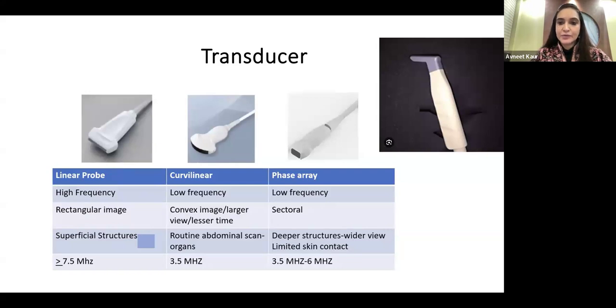So we have three different types of probes available. We have linear probes, curvilinear probes, and phased array probes. And we know that they are all different and can be used for different systems. First we talk about the linear probe. Linear probes have a higher frequency, are rectangular in shape, and are mainly used for superficial structures, and the frequency they use is typically more than 7.5 MHz. Linear probes are typically used for lung ultrasounds, vascular ultrasounds, or musculoskeletal ultrasounds, because they acquire images of superficial structures; the higher the frequency, the better the resolution, and the lesser the depth we are looking at.